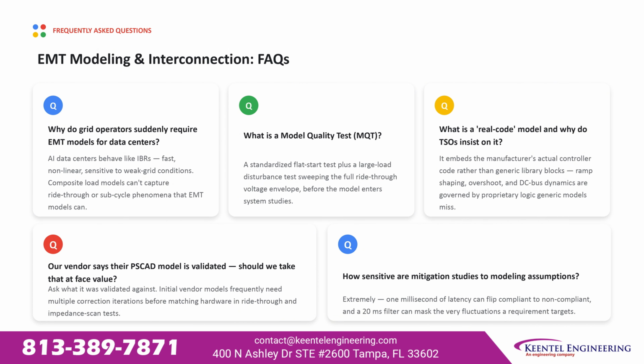What is a real code model, and why do TSOs insist on it? It embeds the manufacturer's actual controller code rather than generic library blocks because ramp shaping, overshoot, and DC bus dynamics are governed by proprietary logic that generic models simply miss. If a vendor says their PSCAD model is validated, should that be taken at face value? Ask what it was validated against. Initial vendor models frequently need multiple correction iterations before they match hardware in ride-through and impedance scan testing.